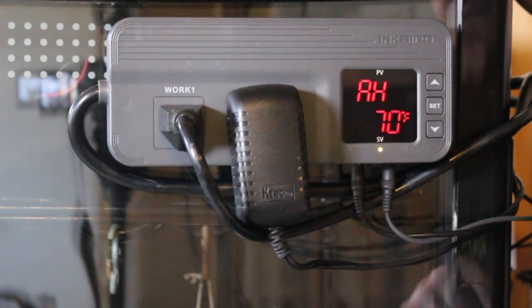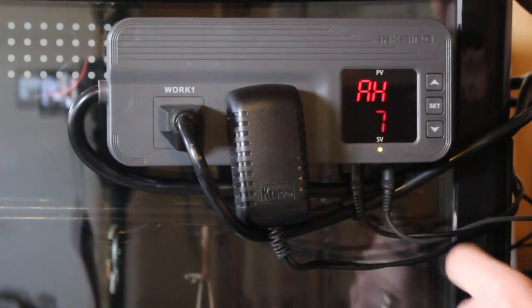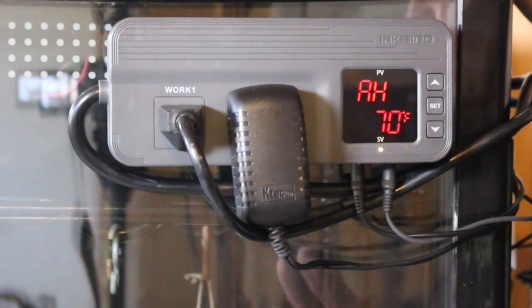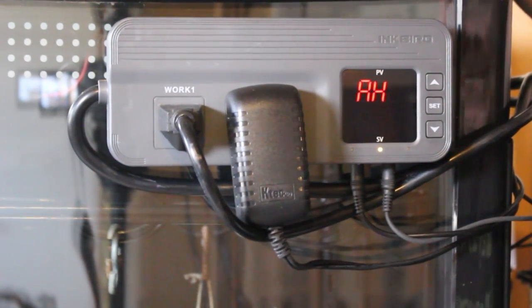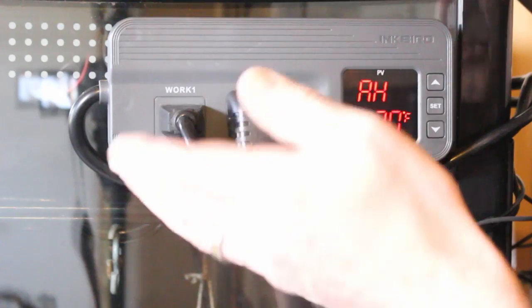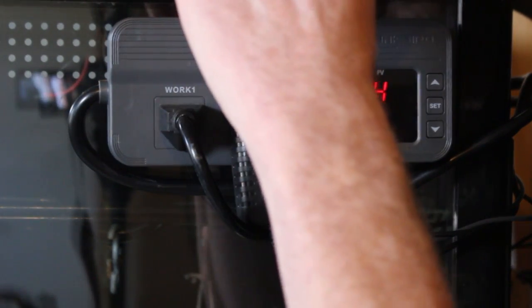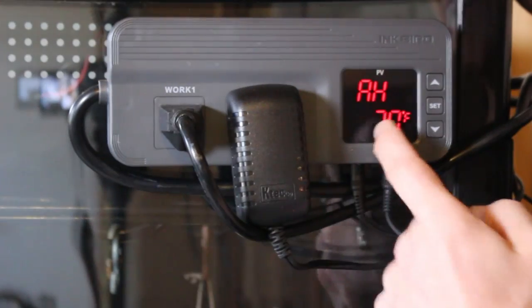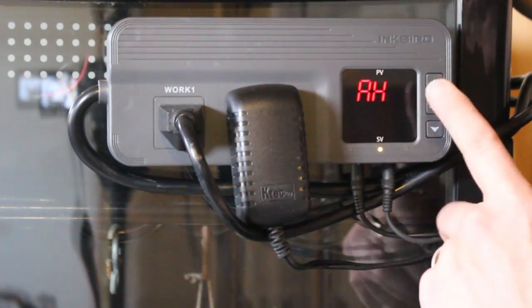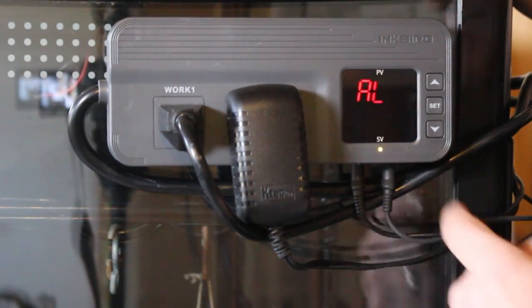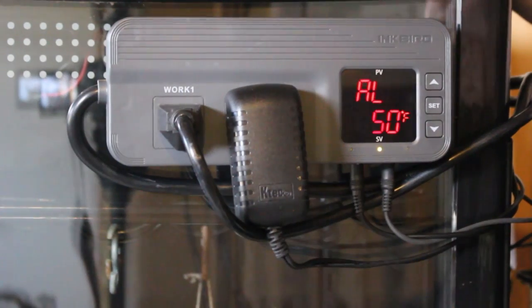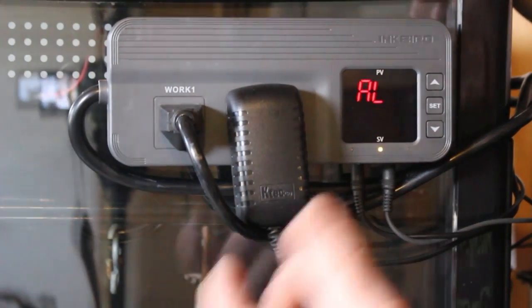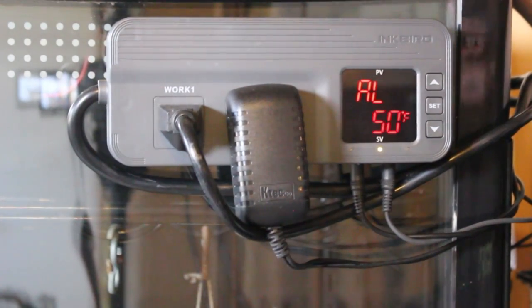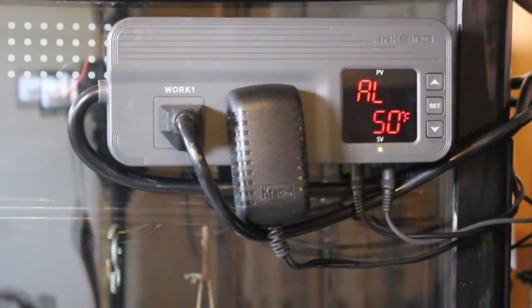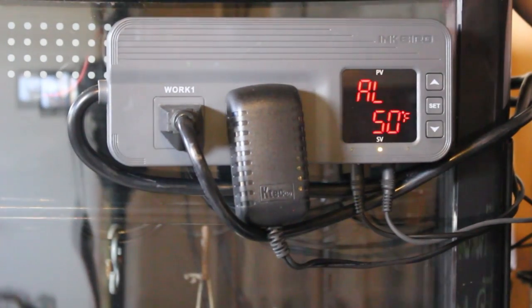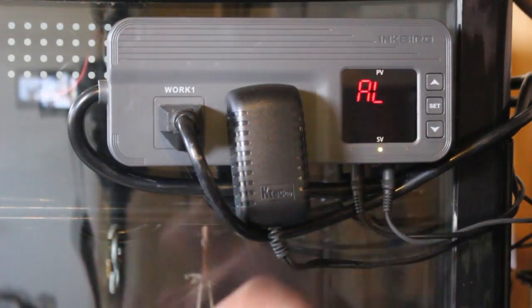It's fine. Here is alarm high. I've got it set to 70 degrees. Essentially, if this thing doesn't cool at 60, it goes past 65, goes up to my differential of 68, and then continues to climb, this alarm is going to go off at 70 degrees. Same with alarm low. I've got it set to 50, that for some reason maybe this controller fails. So it's got built-in settings that it will sense, oh gee, I've left the compressor on too long. It's getting down, temperature's dropping. Let's kick the alarm on. So essentially I've got it set to alarm at 50 degrees and 70 degrees.